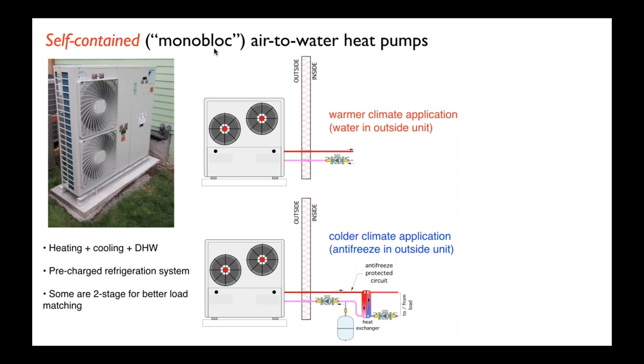In a very warm climate where there's very little chance of freezing, I know in some of the southern European applications, probably some of the southern Asian applications, these units do operate directly with water. In most of North America, especially up where hydronic heating is more common, you have sustained freezing conditions in the winter. And of course, the potential problem is a prolonged power outage with water in the unit. Let's say there's no backup power, there's no heat tracing. Obviously, it's going to freeze and damage the unit. So we can set up the system, and I'll show you examples of systems today that are set up to operate with antifreeze. Many of the manufacturers of monobloc style air-to-water heat pumps require antifreeze. They simply don't want to have their product at the risk of freezing.